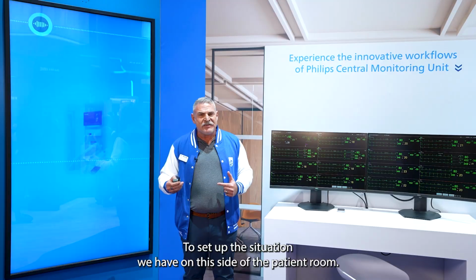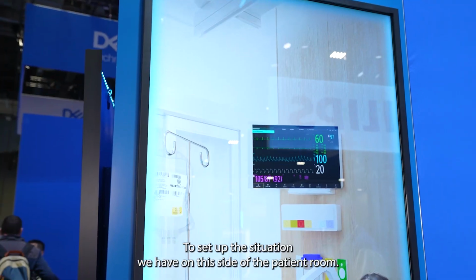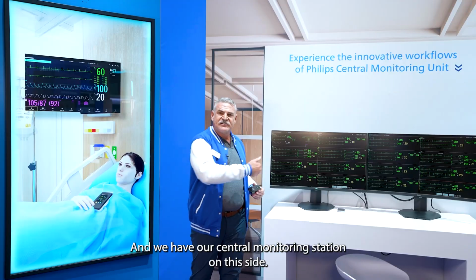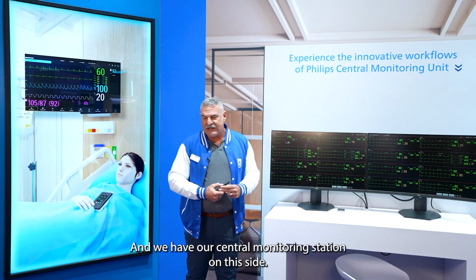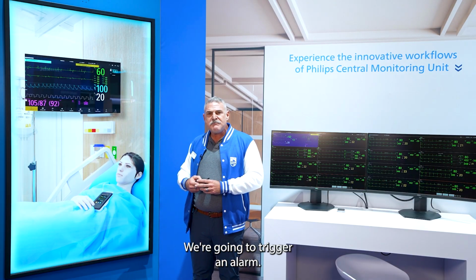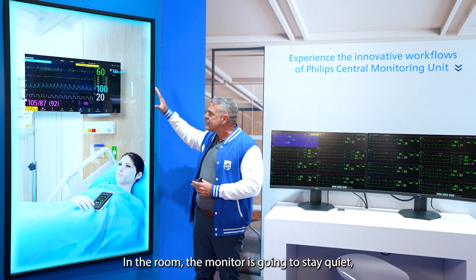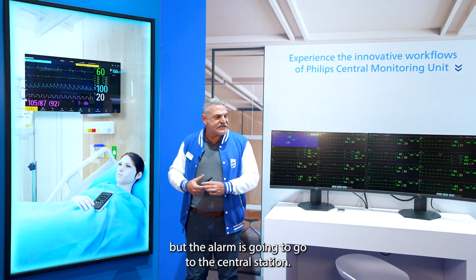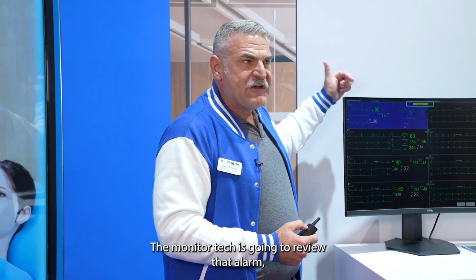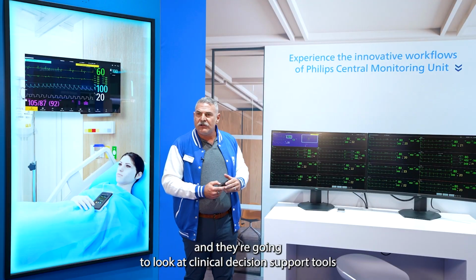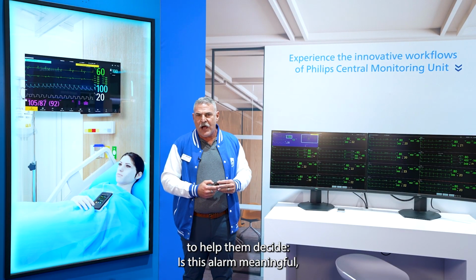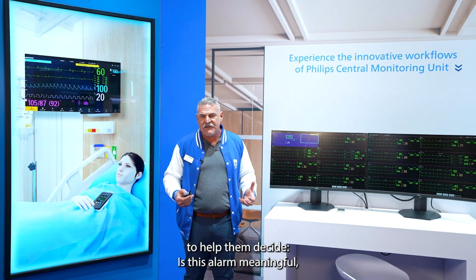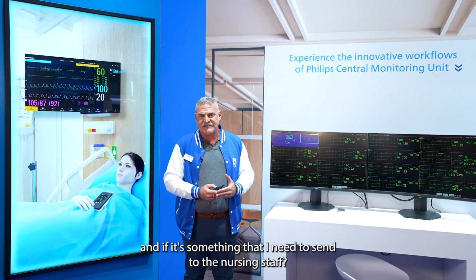To set up the situation, we have on this side the patient room and we have our central monitoring station on this side. We're going to trigger an alarm. In the room, the monitor is going to stay quiet, but the alarm is going to go to the central station.